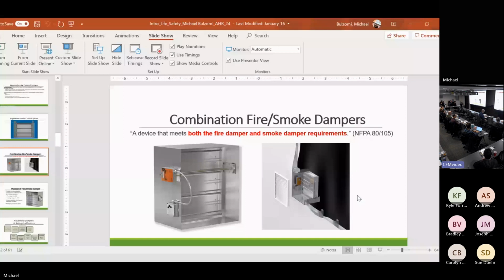The minute it reaches the limit switch temperature of that damper, so if it's a single limit of 250 degrees, the damper's dead. It's part of the wall. I cannot reopen it for smoke control. Once it reaches the fire damper portion of it, it's done. It is now a fire damper, no longer a smoke damper. If there's a dual temperature switch on it, or if it hasn't reached its limit switch, you can still operate it like a smoke damper. Once it reaches its high temperature, it's done.